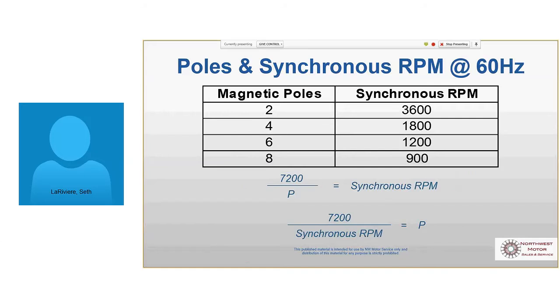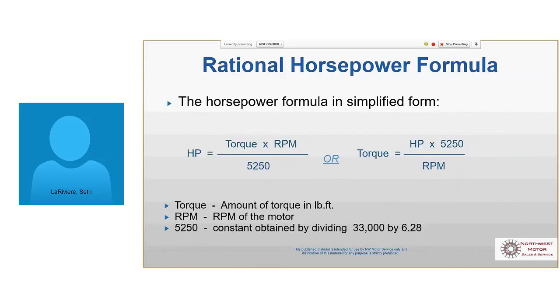Now there's a difference between synchronous RPM. These are all synchronous speeds. The motors don't actually run at that speed. They run slightly slower than that due to a phenomenon called slip. And slip is the torque producing component of the motor winding, so it's really important. We're going to get into that in a minute.